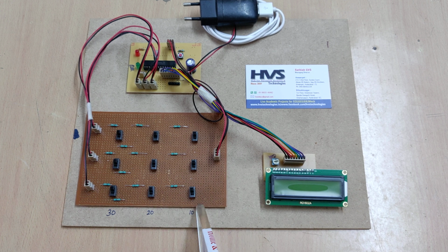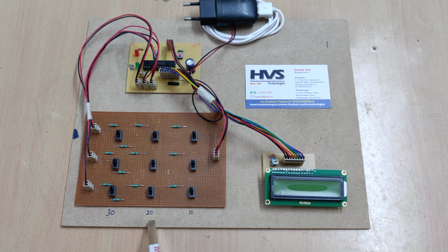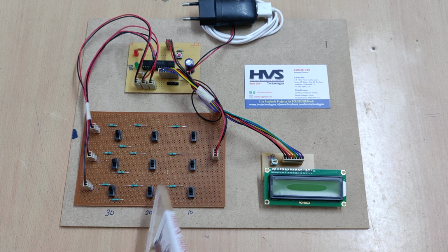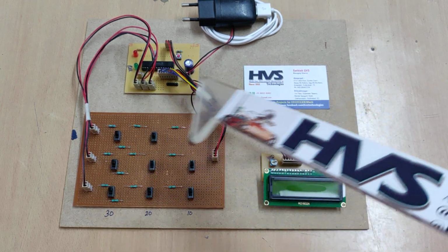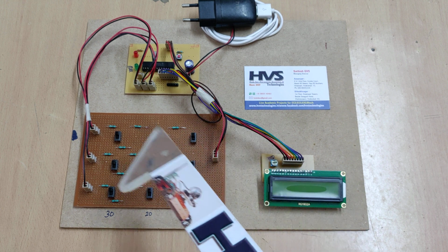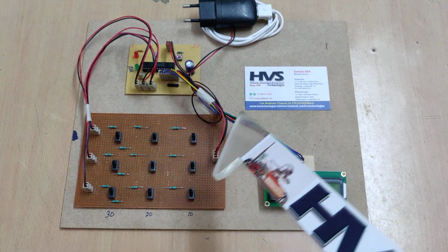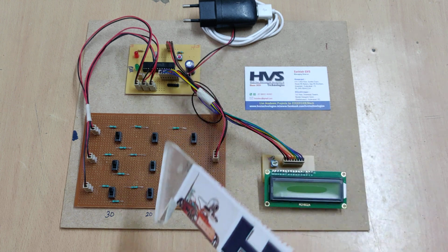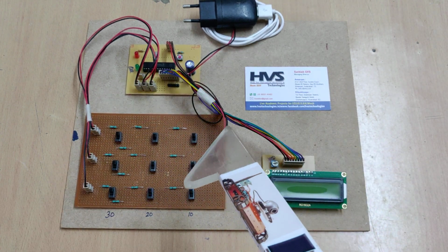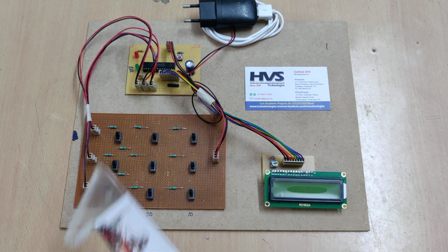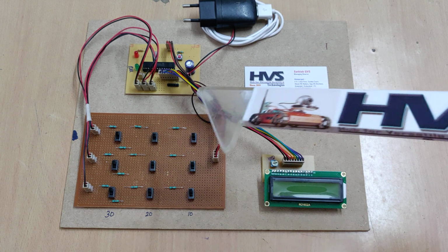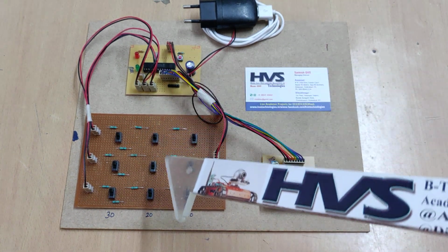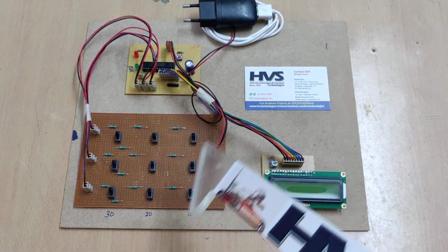From this transmitter point, we have located the short circuit switches at 10 km, 20 kilometers and 30 kilometers. Whenever a short circuit happens, based on the length of the wire in real time, as we know, the resistance is proportional to the length of the cable. Wherever the short circuit happens, we measure the drop voltage, and based on the drop voltage we calculate the approximate distance, and identify at which location and at which line, so line to line fault.